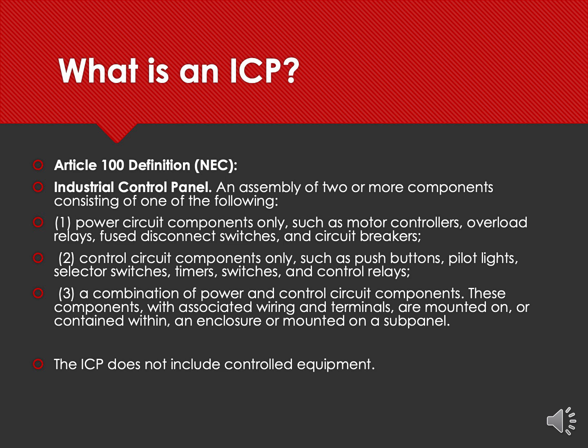In the control circuit side of the cabinet, this is usually the selector switches and time delay switches or relays and control relays. This is sort of the brains of the outfit. This controls the power part of the system and runs things like programmable logic controllers and other devices that are smart things in the system. It is a combination of the two in almost all cases. These components are mounted in the enclosure with the wiring and terminals in it. And the industrial panel actually does not include the equipment that it's controlling. So again, this is the focus of our presentation, and usually it has both power circuitry and control circuitry. Let's go to the next slide.